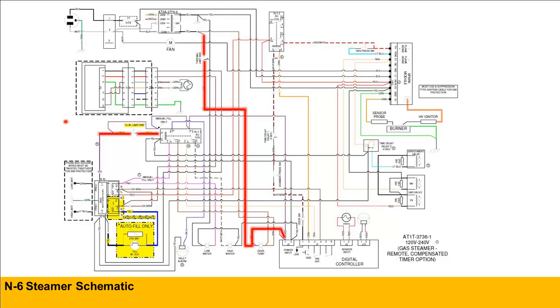Now, in the field, for me, it's always confirm, confirm, confirm. So I'll instruct the technician to take the reed switch offline and plug the violet wire directly into the coil. Now, remember, the violet wire is hot as soon as you plug the unit in. So if we bypass the switch and plug it in and my relay is still not energizing, that's confirmation for me that, yes, I have a defective relay. At that point, we'll give you a part number. You go ahead and order the part through Parts Town and replace it, and the unit should be up and running.